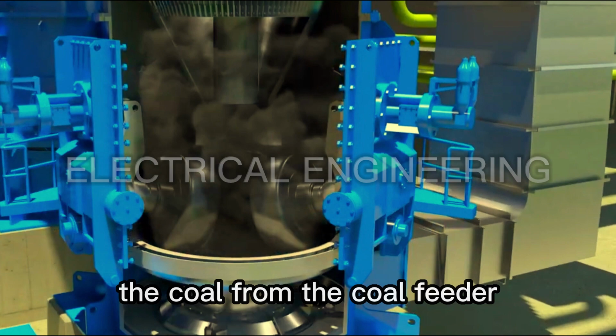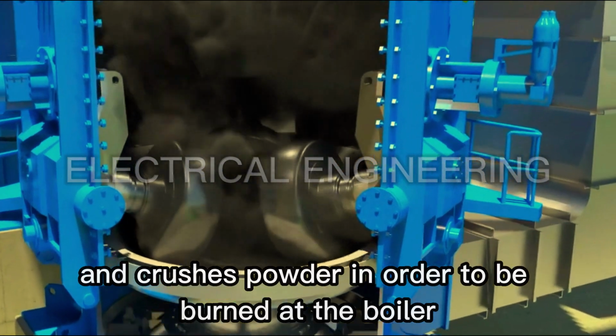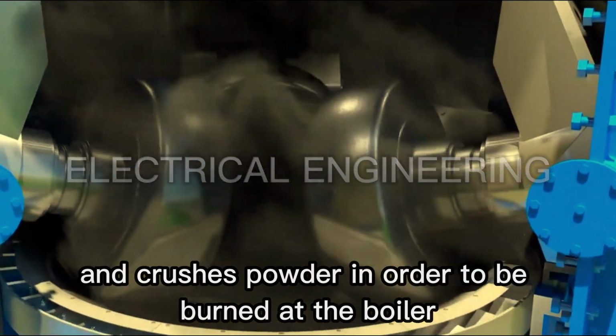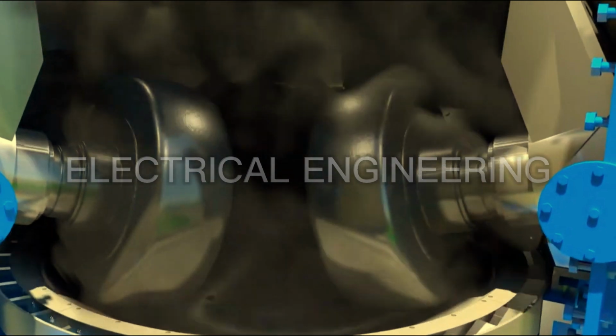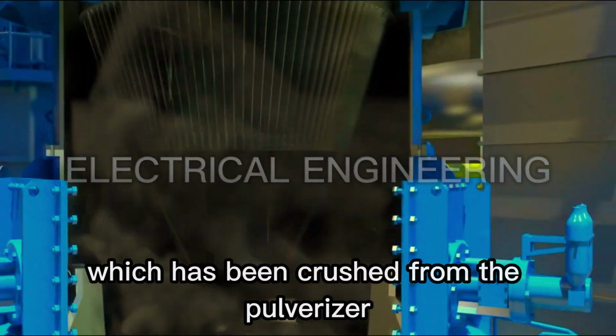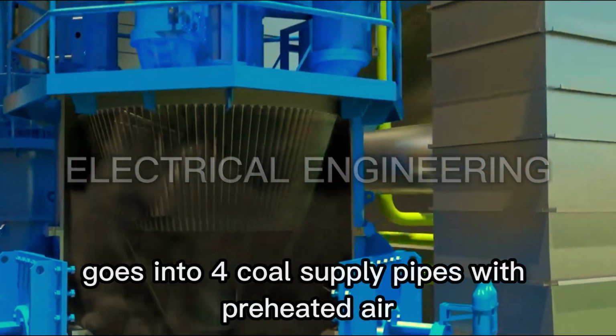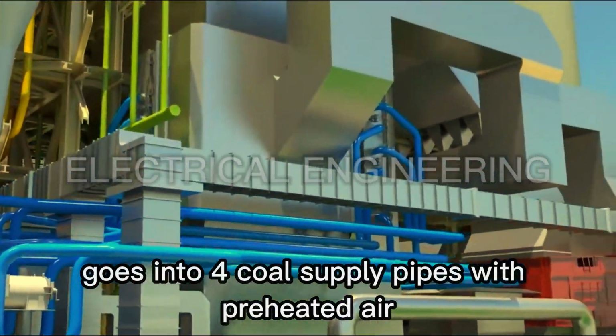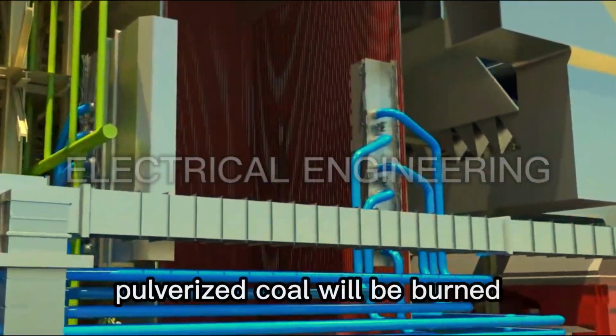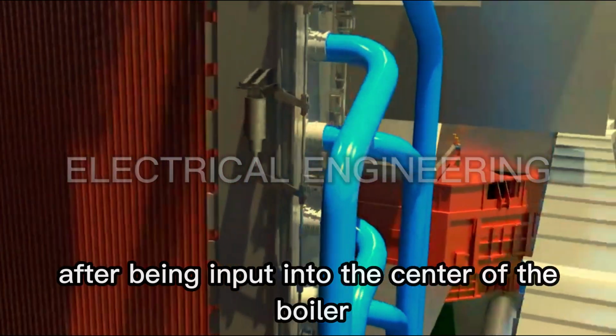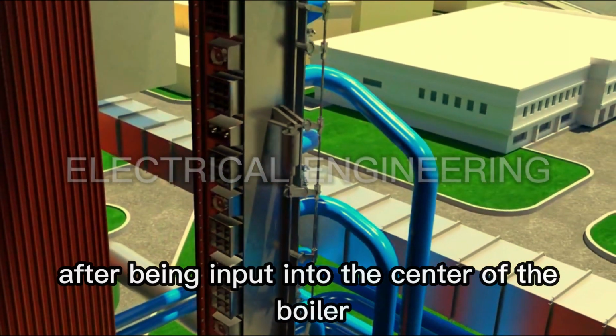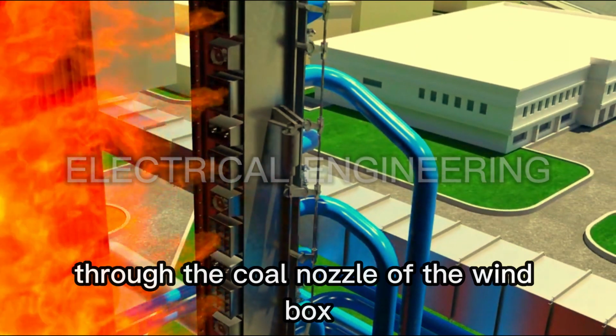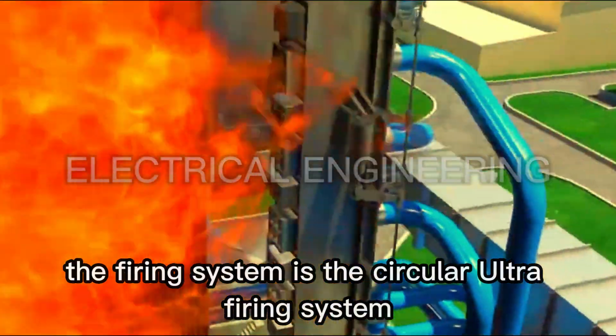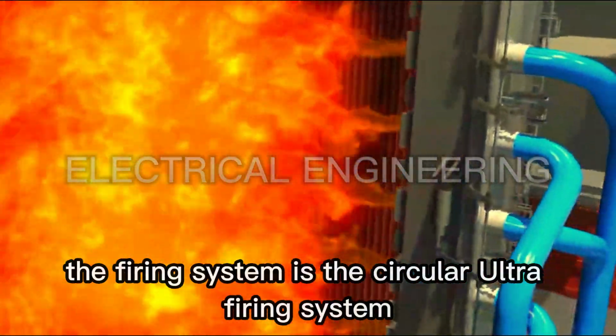Pulverizer is supplied the coal from the coal feeder and crushes it into powder in order to be burned at the boiler. Pulverized coal, which has been crushed from the pulverizer, goes into four coal supply pipes with preheated air. Pulverized coal will be burned after being input into the center of the boiler through the coal nozzle of the wind box. The firing system is the circular ultra-firing system.